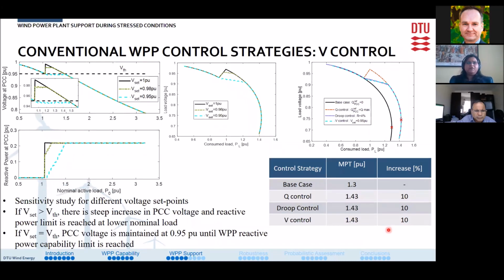Next, we go into voltage control strategy. Here also we did a sensitivity study for different voltage set points. So we see here if the voltage set point is greater than the threshold value, which is this one here, then there is a steep increase in the PCC voltage. However, if we set the set point at the threshold voltage, then the PCC voltage is maintained at 0.95 until the wind power plant reactive power capability is reached here. Again, when compared to the previous two strategies, it gives the same maximum power transfer, and that's mainly because in all three cases, the maximum reactive power capability limit of the wind power plant is reached.